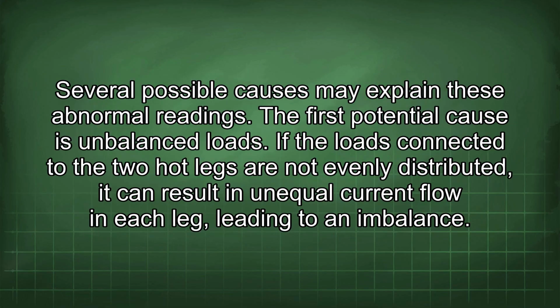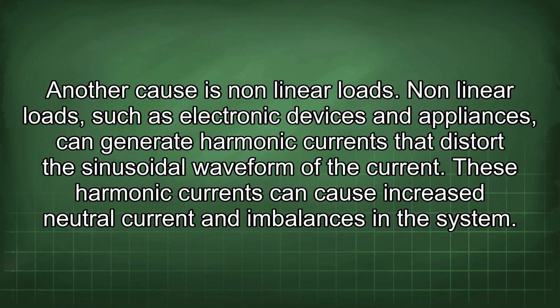Several possible causes may explain these abnormal readings. The first potential cause is unbalanced loads. If the loads connected to the two hot legs are not evenly distributed, it can result in unequal current flow in each leg, leading to an imbalance. Another cause is nonlinear loads. Nonlinear loads, such as electronic devices and appliances, can generate harmonic currents that distort the sinusoidal waveform of the current. These harmonic currents can cause increased neutral current and imbalances in the system.